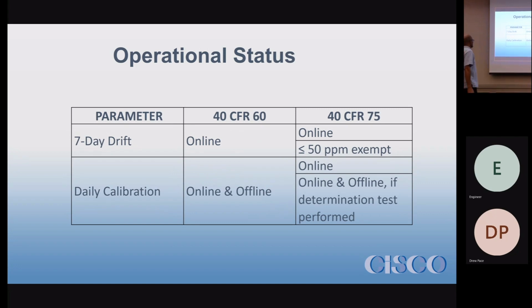Operational status for the 7-day drift test. The unit has to be online, basically combusting fuel. Part 75, same thing, online. Under 75, if you have a span that's less than 50 ppm, you're exempt from the 7-day drift test. And we're going to address that issue regarding the 7-day drift test on a different slide.